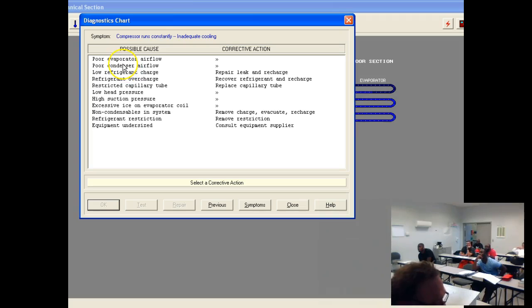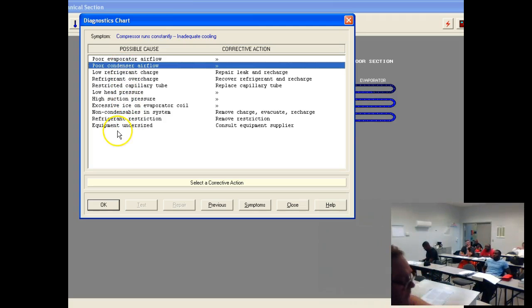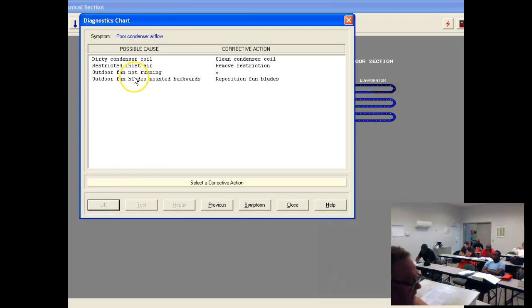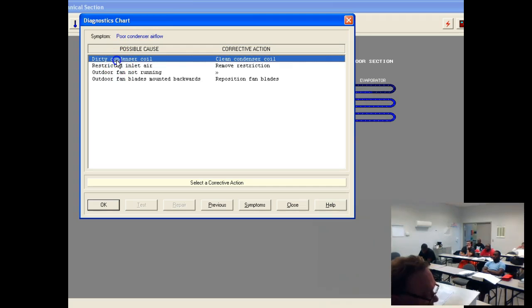When you do, let's say, poor condenser airflow. Now, I don't suspect this, but it's a possibility because, remember, we're running off of, it doesn't do a good job, and it runs all the time. But I know that should probably be high head pressure. But anyway, I'm going to hit OK. The causes of that are 4 other possible causes, right? And so you could select any of them, and on some of them, once you select them, there's a test button.